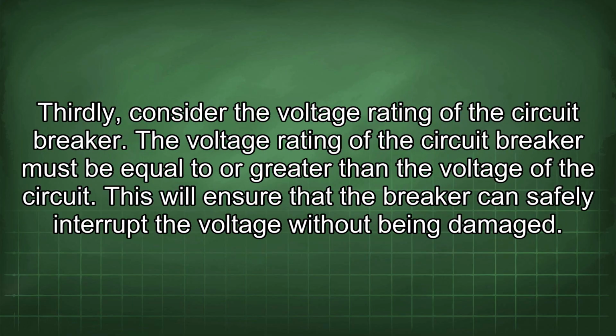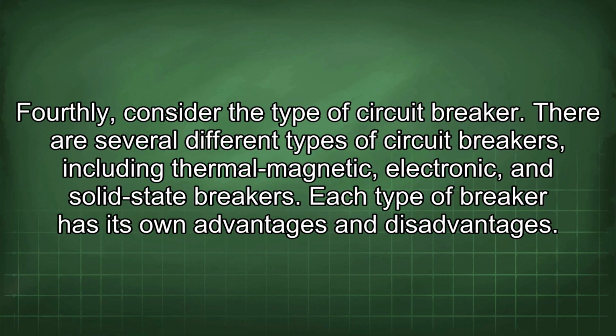Thirdly, consider the voltage rating of the circuit breaker. The voltage rating of the circuit breaker must be equal to or greater than the voltage of the circuit. This will ensure that the breaker can safely interrupt the voltage without being damaged. Fourthly, consider the type of circuit breaker. There are several different types of circuit breakers, including thermal-magnetic, electronic, and solid-state breakers. Each type of breaker has its own advantages and disadvantages.